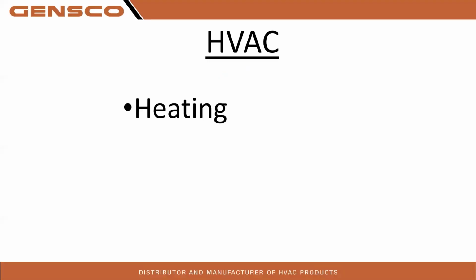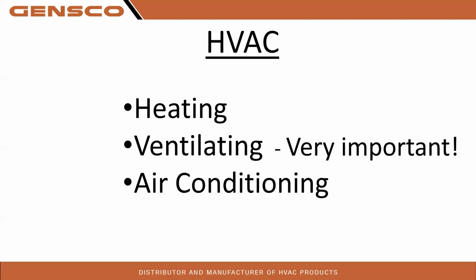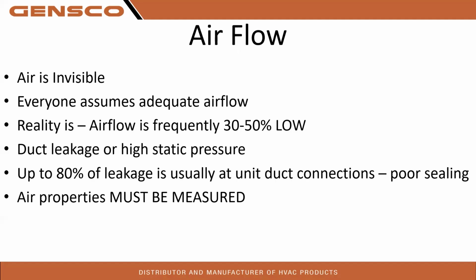HVAC, what does the HVAC actually stand for? We got heating, we got ventilating, we got air conditioning. So on the ventilating side, airflow is very important. Airflow throughout the board. So the air is invisible. Everyone assumes we have adequate airflow, but reality is airflow is 30 to 50% low. We see it a lot. Undersized ductwork is quite a nuisance here, especially here in the Northwest, where we're geared up just for heating.